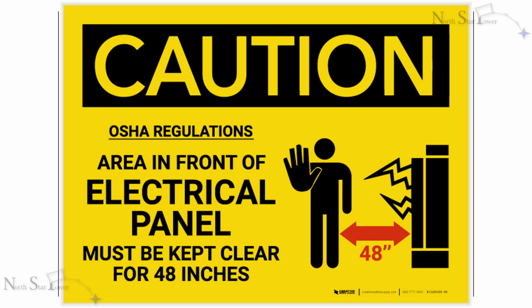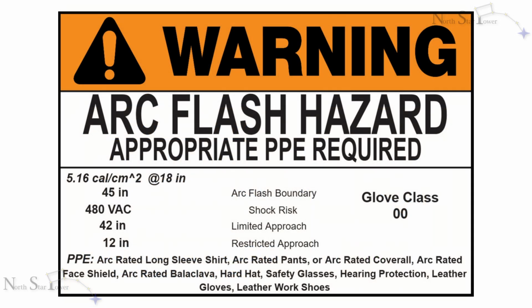The next thing to look at would be the environment the electrical equipment is in. Breaker panels must be cleared by certain footage based on the rated voltage. The NFPA 70E 130.5 and IEEE 1584 also define standards for shock hazard and arc flash analysis for substations. If these studies have been performed, they are identifiable by a label on the substation panels. These studies are now mandatory, but many substations are still out of code today.